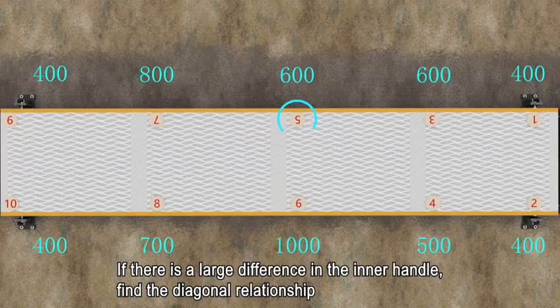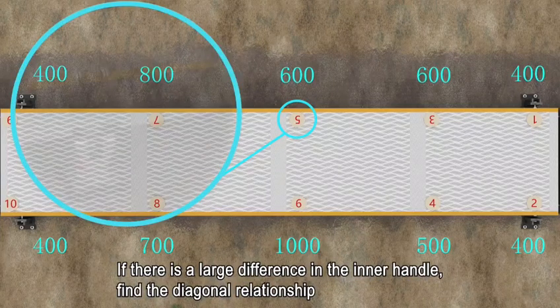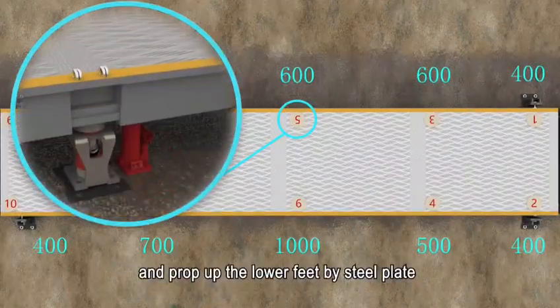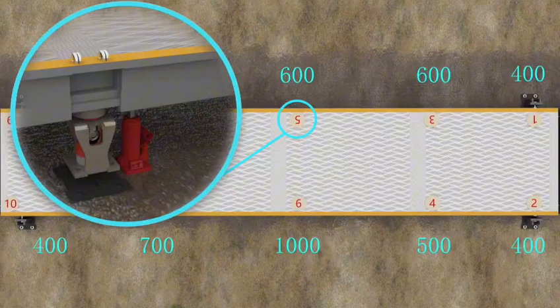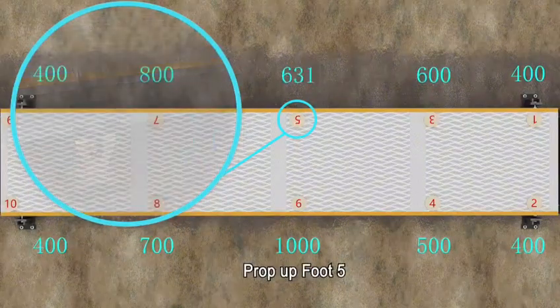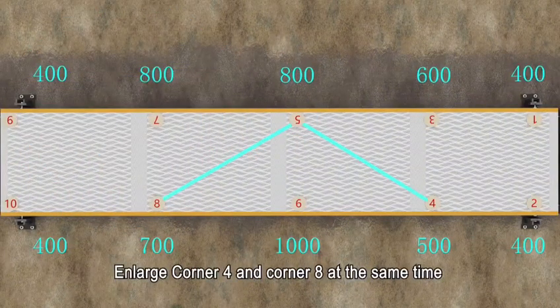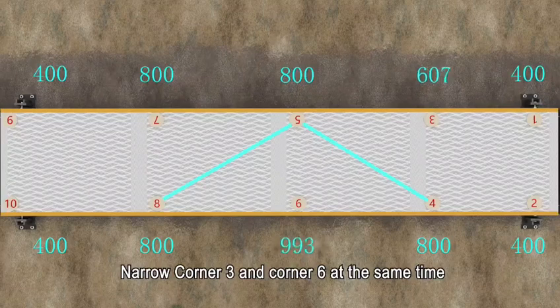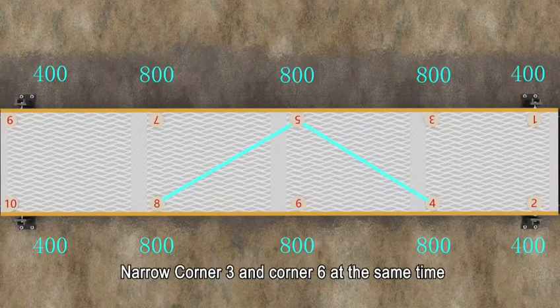If there is a large difference in the inner handle, find the diagonal relationship and prop up the lower feet by steel plate. Prop up foot 5. Enlarge corner 4 and corner 8 at the same time. Narrow corner 3 and corner 6 at the same time.